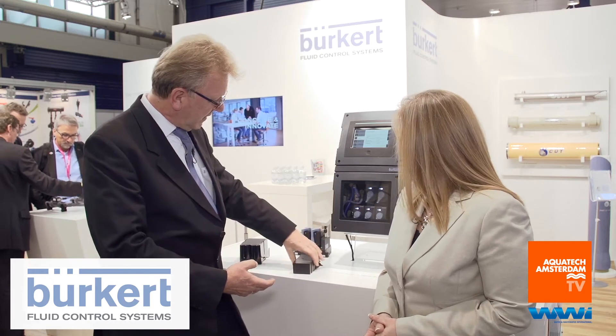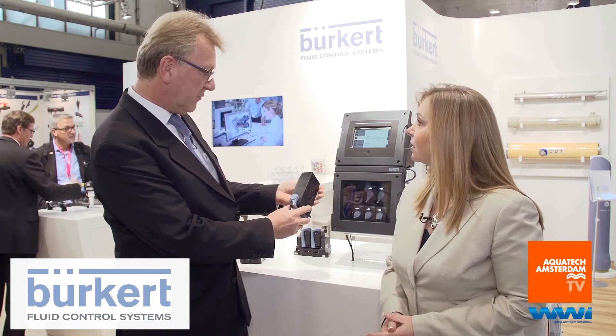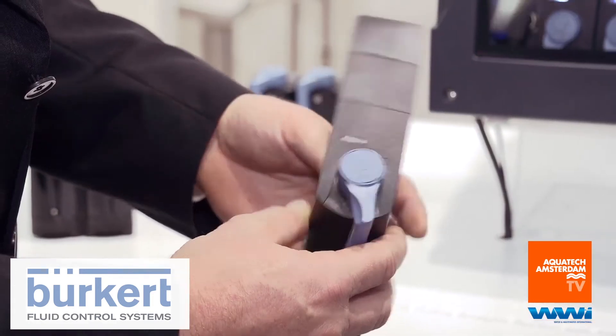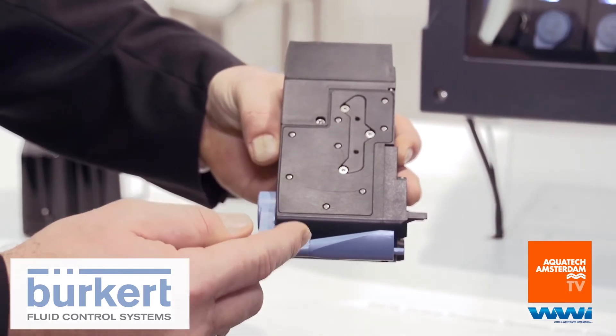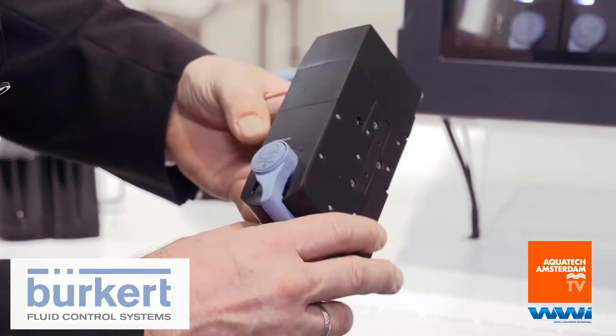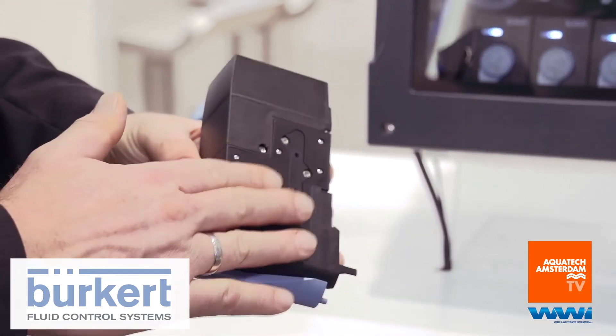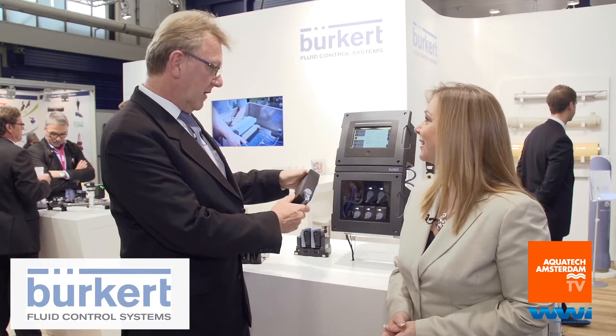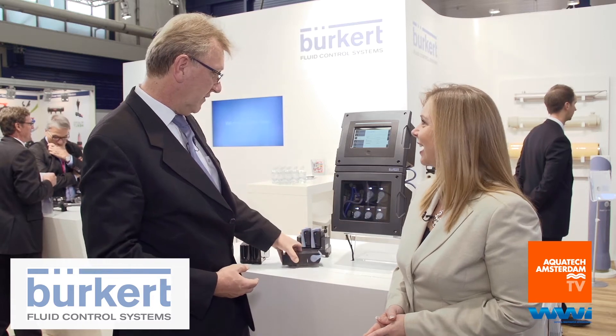Also new is the SAC measurement — it's a spectral absorption coefficient at 254 nanometers, which represents spectral absorption, and in clean water it relates to the total organic carbon. It's a full spectrometer built into the cube. This is very new and we are presenting it here for the first time at this show.